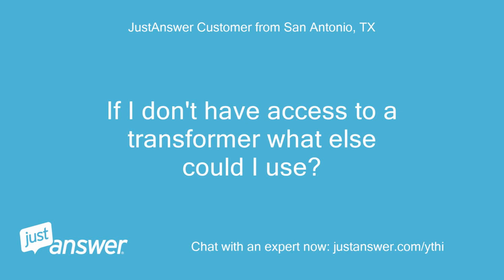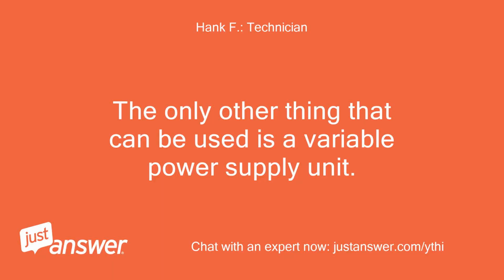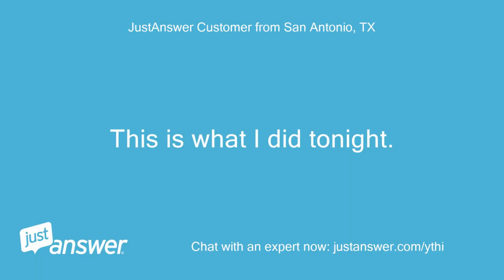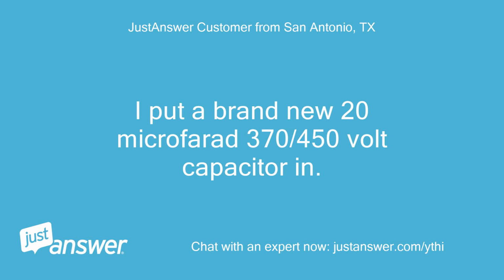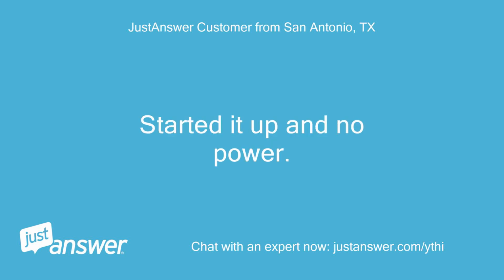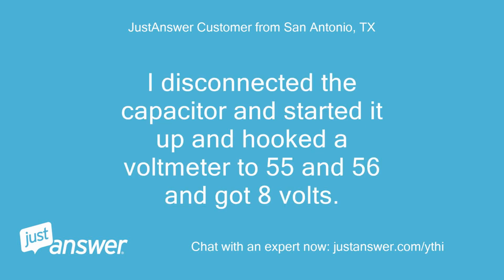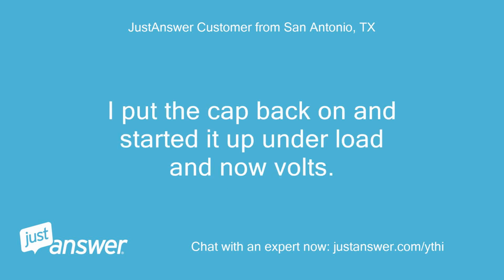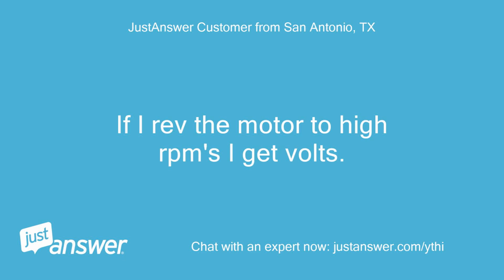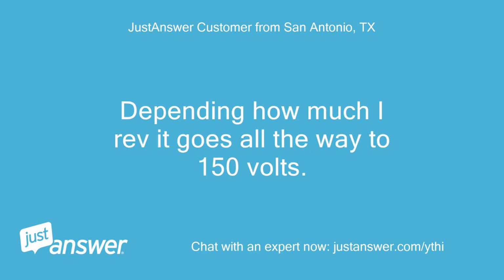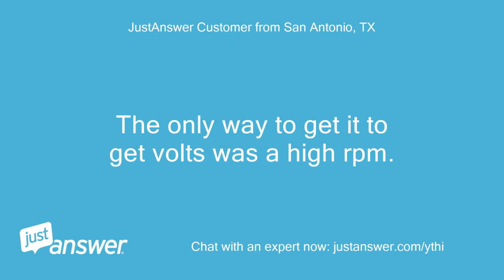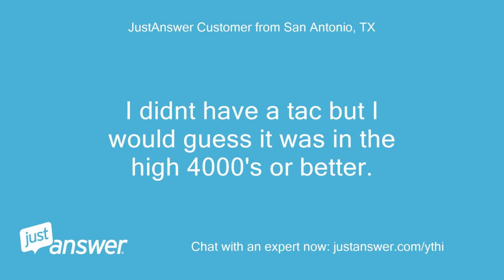If I don't have access to a transformer, what else could I use? The only other thing that can be used is a variable power supply unit. This is what I did tonight. I put a brand new 20 microfarad 370-450 volt capacitor in. Started it up with no power. I disconnected the capacitor and started it up and hooked a voltmeter to 55 and 56 and got 8 volts. I put the cap back on and started it up under load and no volts. If I rev the motor to high RPMs, I get volts. Depending how much I rev, it goes all the way to 150 volts. The only way to get volts was a high RPM. I didn't have a tach, but I would guess it was in the high 4000s or better.